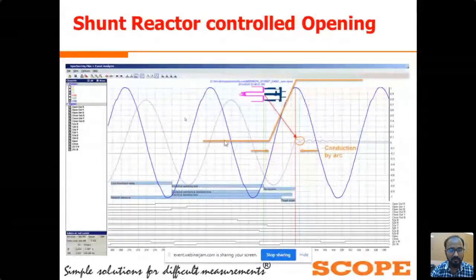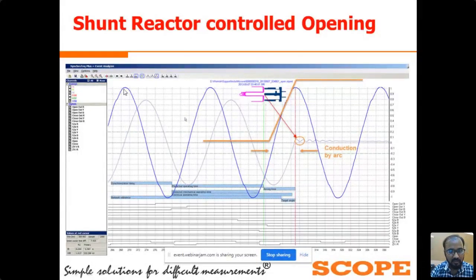So here you can see the waveform in dark blue. This waveform is continuous. This is the system voltage waveform, and you can see here the waveform breaks. This is the current waveform, and you can see the line in orange. This is the dielectric strength between the CB contacts. So here at my cursor position, this is the synchronization delay.